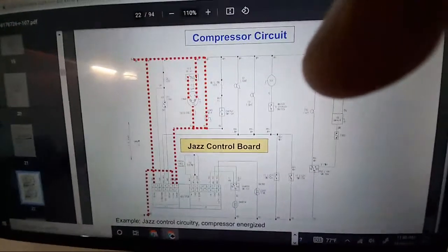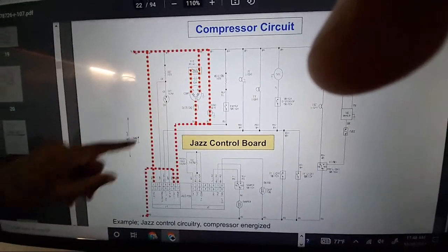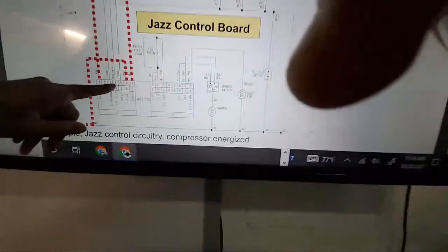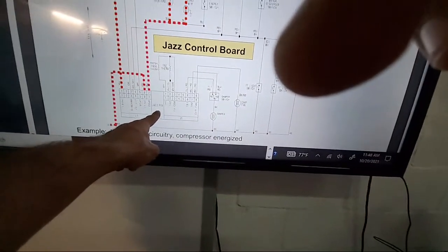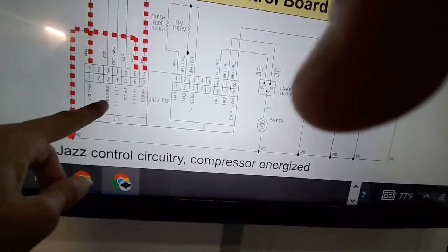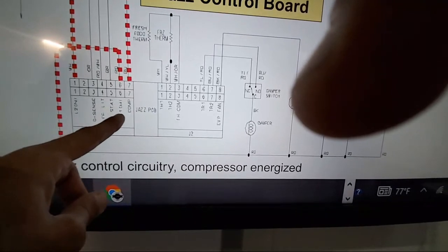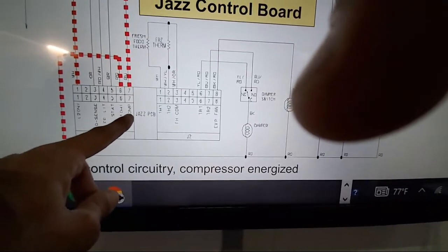All right, step over now. Come here, brother. Show me what he did. Okay. That defrost heater, we want to check it from the board. We want to know if it's operating. Here's our board, Jazz PCB, printed circuit board. Look at what they're telling us on here. L1, defrost, FF, stat, L1, COMP, compressor. They're telling us little things, but let's look for the heater.